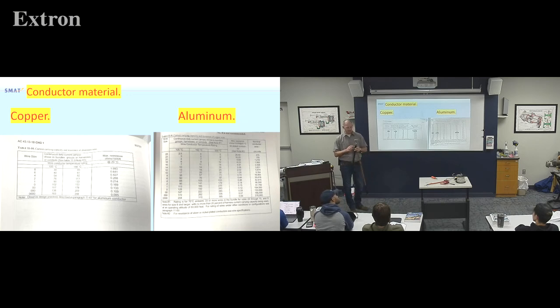Every once in a while you'll see where they were like, hey, we can save like 2 pounds if we run aluminum wire. And they'll run an aluminum wire from the back up to the front. But in order to carry the same capacity, in this case they might run a 4 gauge where they can get essentially the same amperage out of their aluminum wire. And it'll still be lighter, but with the various strength, corrosion, and other issues with aluminum, you just don't see it much anymore. But you do need to be aware that whatever material your conductor is, whatever material your wire is, you got to be on the right chart and have the right one.